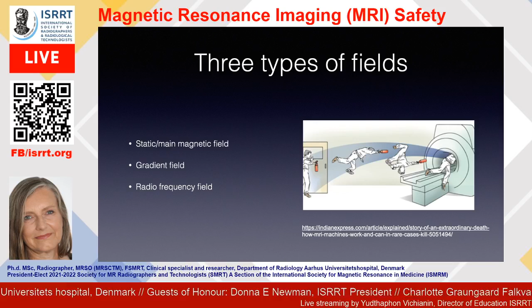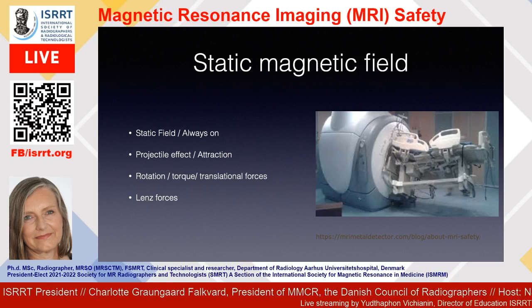The static magnetic field is always on, and that's responsible for the projectile effect or the attraction. It's also responsible for rotation and torque or translational forces and the Lenz forces. The gradient fields are time varying, and they are accountable for the acoustic noise. And this is why I use this image.